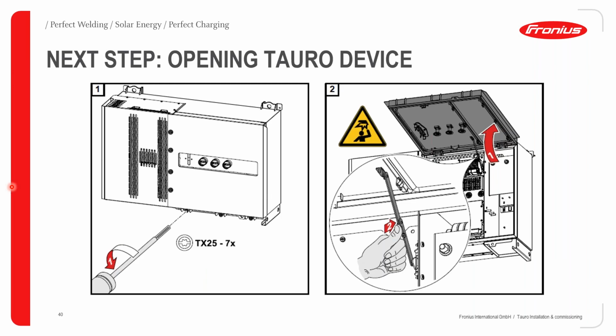Once you have your Tauro mounted, the next important step will then be to open up the Tauro in order to do your AC and DC connections. Okay, so what you need to do is we suggest that you do use a Torx screwdriver. Okay, so a Torx 25 screwdriver, you need to remove the outer screws. Once you've done that, you then open up the bonnet of the inverter. Let's call it that. The reason I'm calling it that is because it's very similar to how the bonnet of a car works. When you open up the bonnet of a car, you need to secure it somehow. And with the Tauro, the securing is done via a lever. So please make sure that you do click that lever into place. Okay, and this will prevent the shell of the Tauro falling on you when you are doing connections.